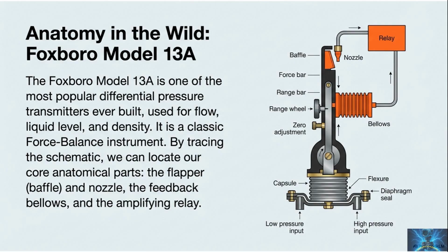The Foxboro Model 13A is a famous differential pressure transmitter used for flow, liquid level, and density. It's a classic force balance instrument you can understand by tracing the core anatomy. The capsule senses high pressure and low pressure and creates a small mechanical force. That force positions the baffle near the nozzle, creating a back pressure signal. The bellows and amplifying relay complete the feedback loop and produce a strong pneumatic output.